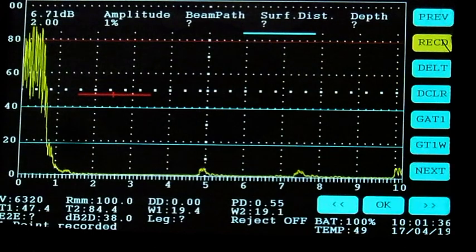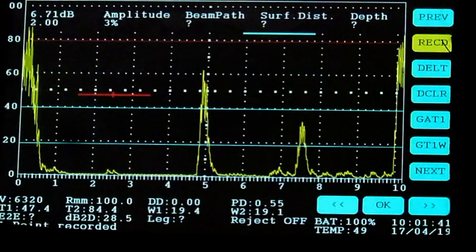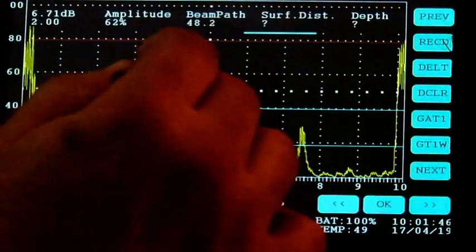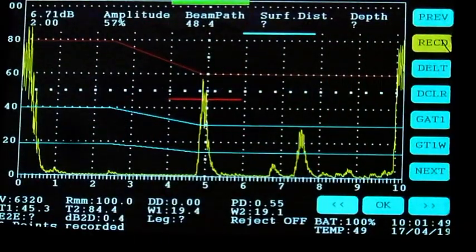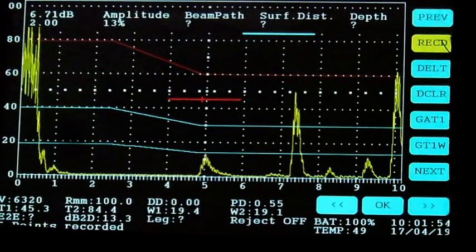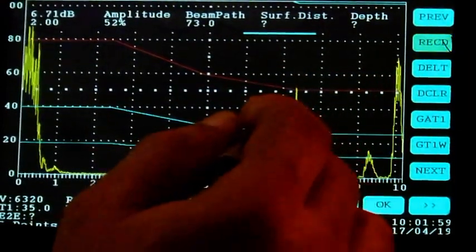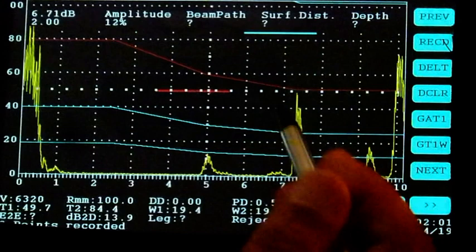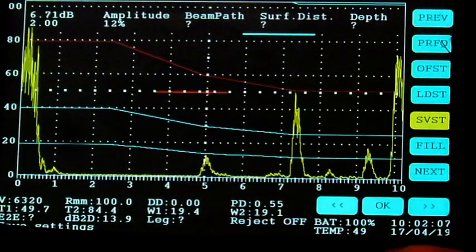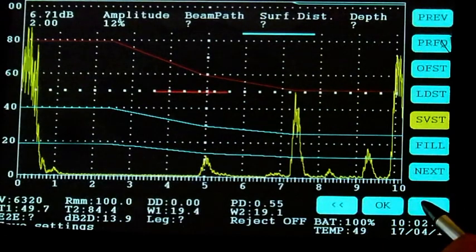Then move over to the second point, pick up an echo, maximize it and gate the signal, and then click record. Move over to the third point, maximize the signal, gate it and then record. So you have a three-point DAC been made. The instrument can actually take up to 14 points for a DAC. Using the same block, we can also construct a TCG.